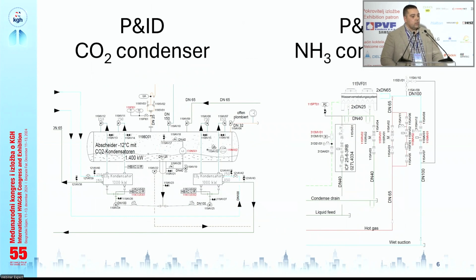On this slide, you can also see some more details about the P&ID, but since we are pressed for time, I will just briefly go through it. I would just mention this ammonia condenser, which is now horizontal type, and as you can see, there is a very complex system of valves and valve stations with different sensors that allow us fully automatic running of the system and the transfer from the standard refrigeration system to the heat pump mode.